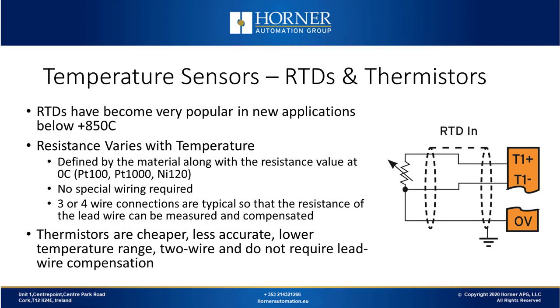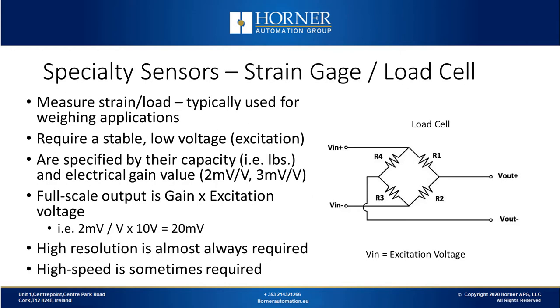With thermistors, resistance also varies with temperature, but they're cheaper, less accurate, and typically have higher resistance values. For strain gauge and load cell type sensors, they measure strain or load, typically used in weighing applications. From the diagram on screen, what you're really looking at is a Wheatstone bridge. You have an input voltage called an excitation voltage. The load cell has a gain associated with it, typically expressed in millivolts per volt, and then it has an output from the bridge, which is what is measured. The full scale output is the gain of the load cell times the excitation voltage, which is typically around 10 volts. High resolution is almost always required because you're usually using low voltage levels.